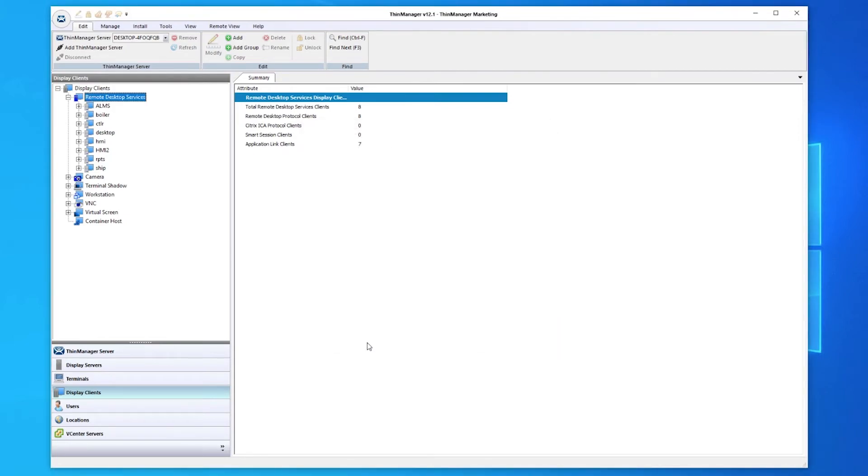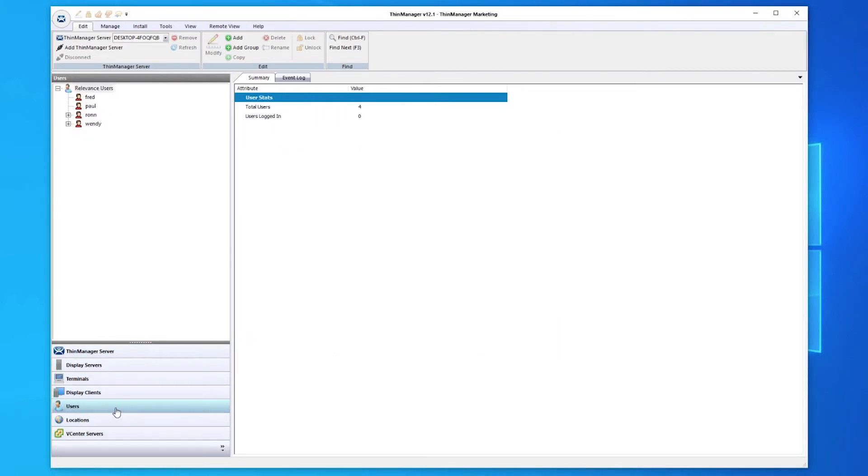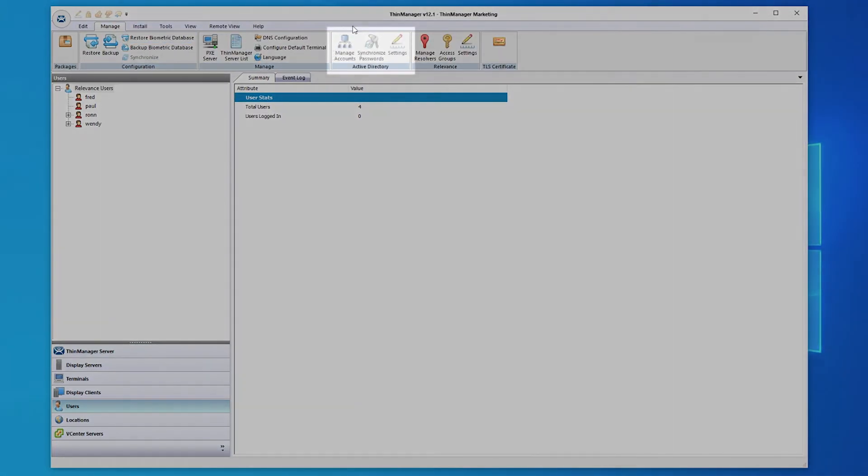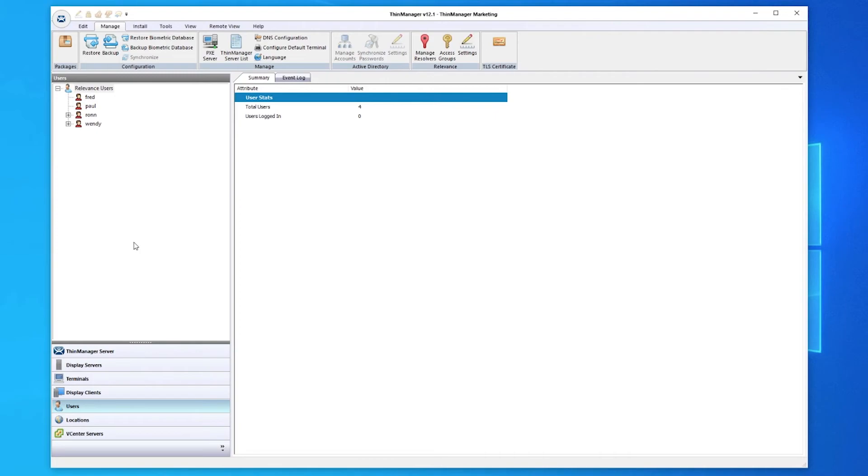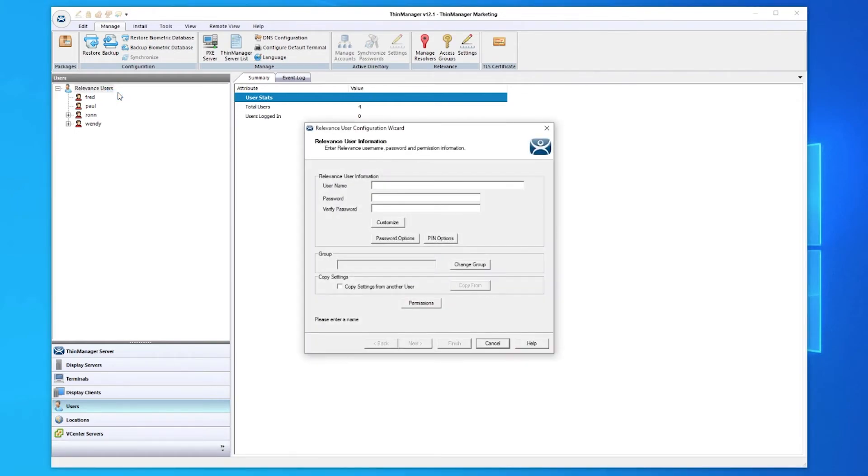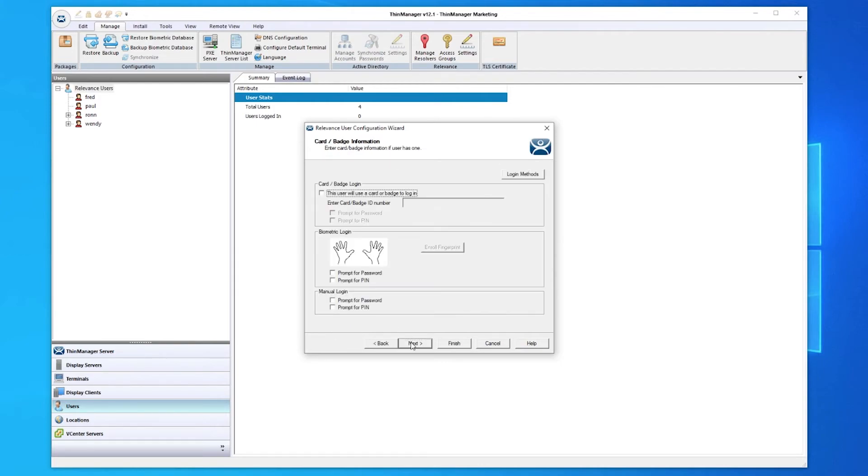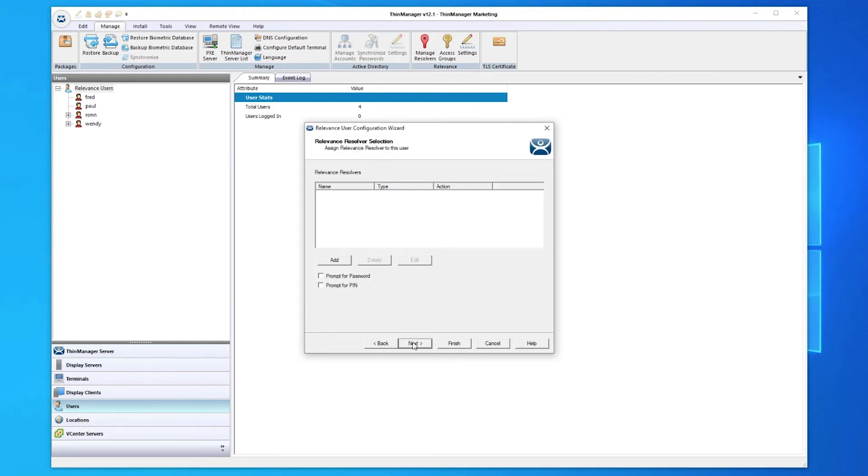Next are your users. This can be synced to your Active Directory by using the Active Directory submenu section in the Manage menu of the top ribbon bar. Users can be set up in a similar way as a terminal or display client using the Configuration Wizard. Each user is given different options for authentication, such as password, PIN, ID badge, or even biometrics. Display clients can be assigned to the user upon authentication or the group of users, such as a maintenance group.